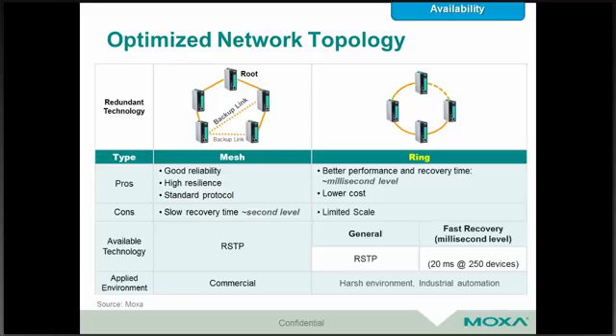Again, what we're seeing a lot more in smart factories is this ring topology for redundancy. On this type of topology, you're talking millisecond level recovery time, and it also tends to be lower cost. The problem with ring topology is that, A, you have limited scale, and B, these are typically isolated to a single hardware vendor, which means that if you have different vendors of hardware within your factory, you typically can't use this type of topology with those vendors together. There are also some general standards with fast recovery, and again, RSTP at 20 milliseconds. So you can definitely see the difference, and that ring topology is a lot more appropriate for industrial or mission-critical applications.